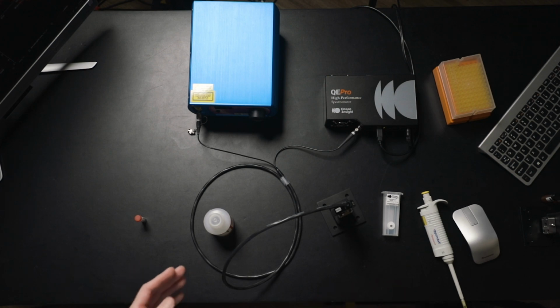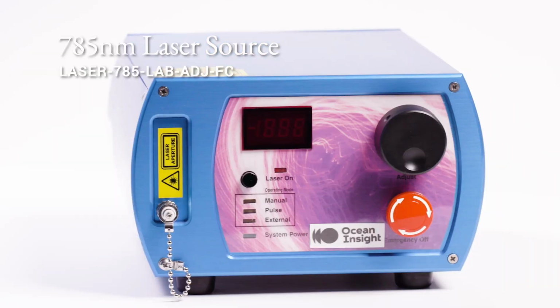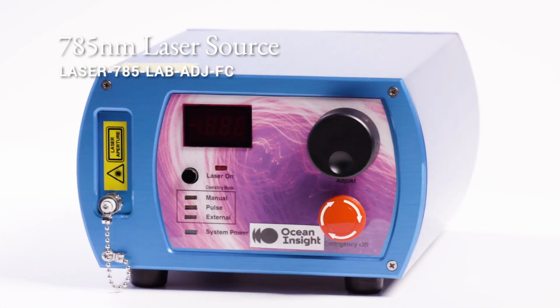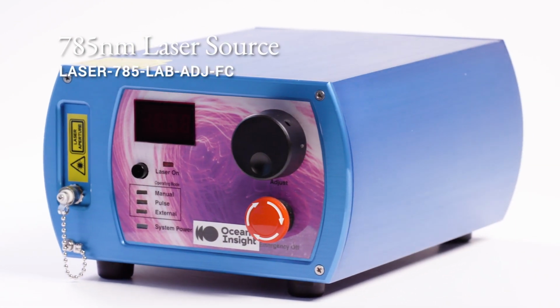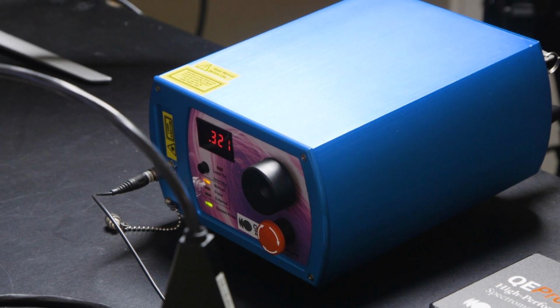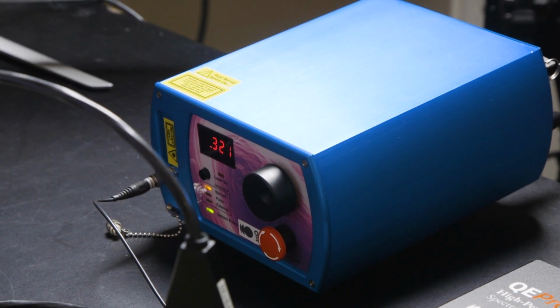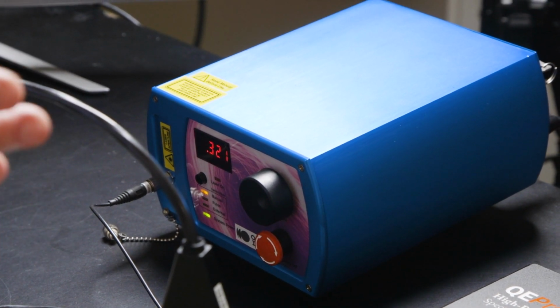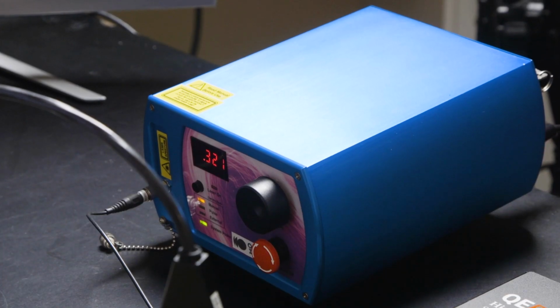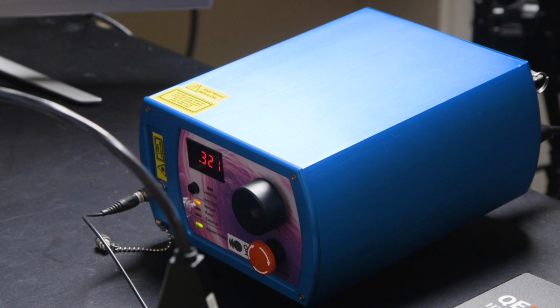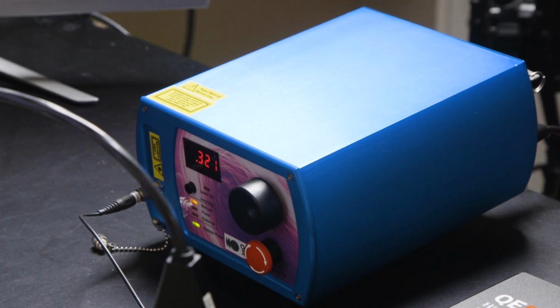So this includes our laser source, the 785 laser source. We can see here on the front of the display, we have some numbers shown in red, and this is an arbitrary power output for this unit because this offers adjustable power. We want to make sure that we have enough power to get signal, but not so much that we're burning the sample. So we have it right now set to 0.321, which is a bit arbitrary, but is equivalent to roughly 25 milliwatts of power.